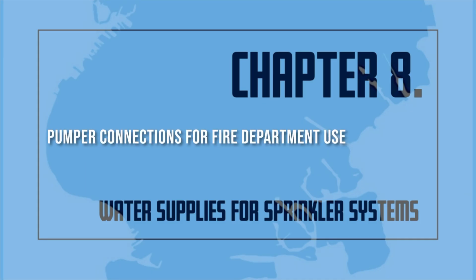Pumper connections for fire department use. Normally, a sprinkler system is connected to an automatic water supply source. Auxiliary sources of water are supplied through fire department connections at the building. Fire department connections are a standard part of most sprinkler systems. When responding to an alarm, most fire departments supply water to the standpipe system first. The standpipe system supplies water to the fire hoses to be used within the building. Water is then supplied to the sprinkler system through its own fire department connection.